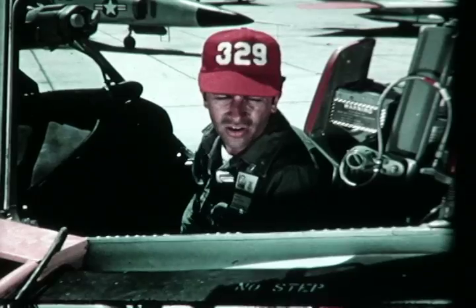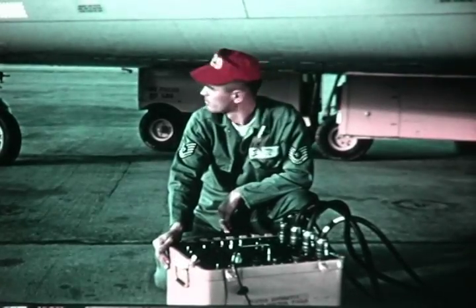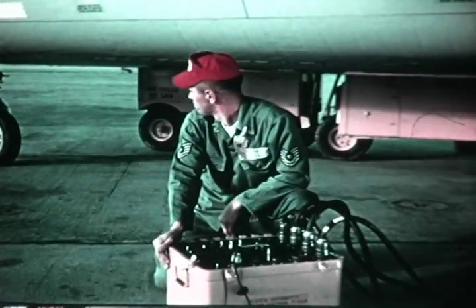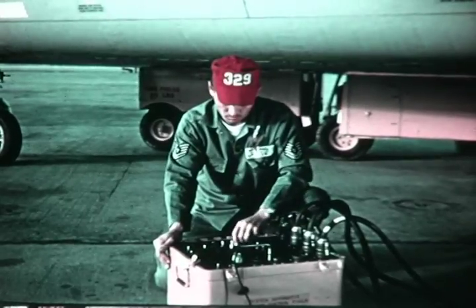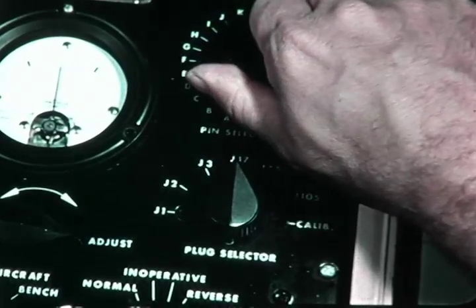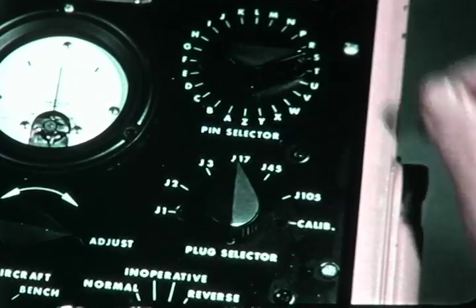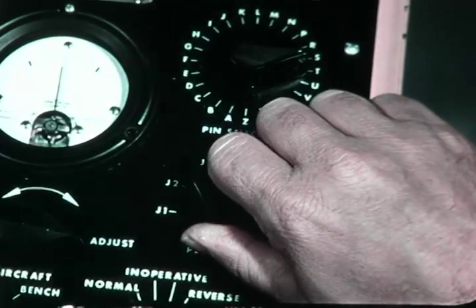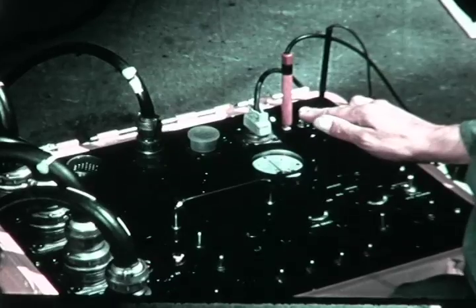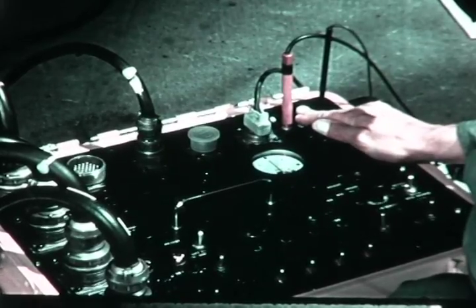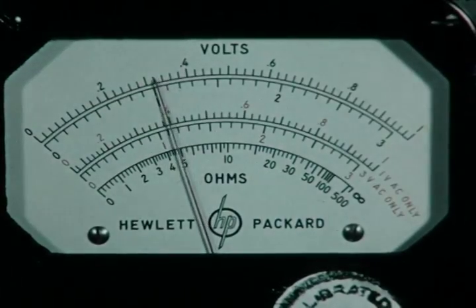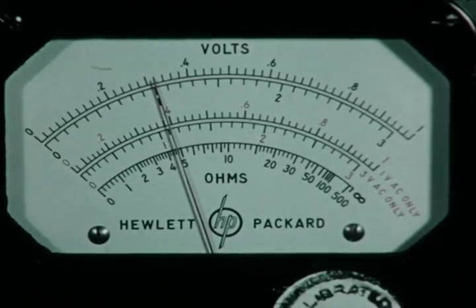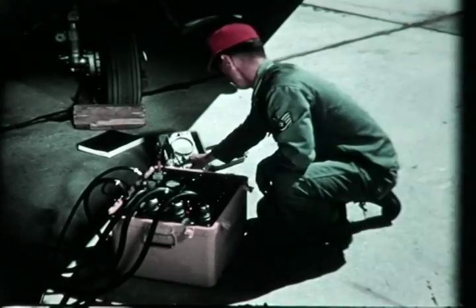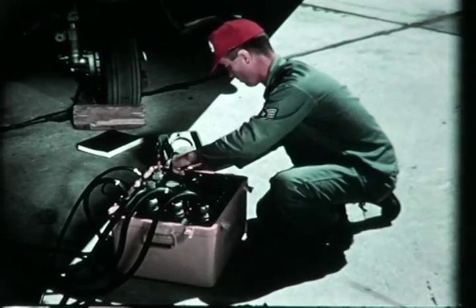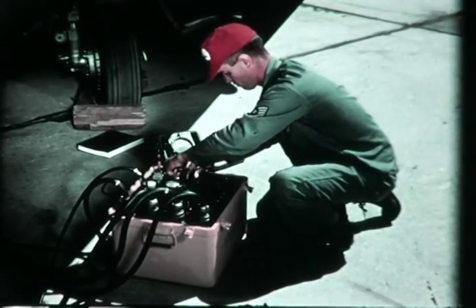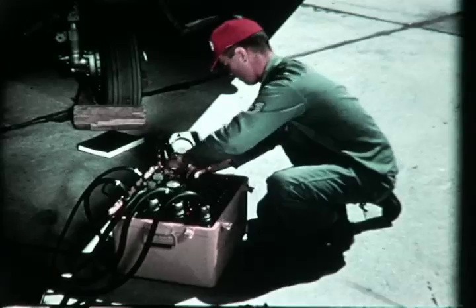Now, to check our damper plus and minus 105 voltage. Set the VTVM to plus 300 volt DC scale. Turn the pin selector to T, place the plug selector to J2, and lift the lift to read switch. The VTVM must read 93 to 117 volts, or calibrations will be off. In the same manner, we test the damper minus 105 volts using the J3 plug.